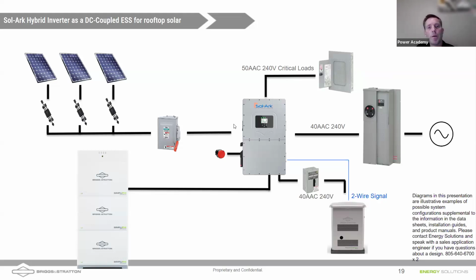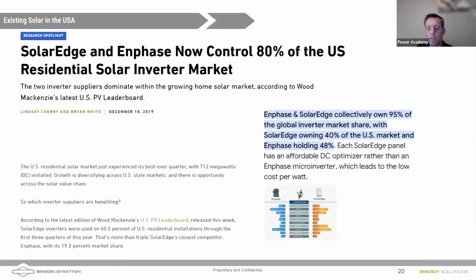This DC solar is then fed through a disconnect into the Sol-Ark. There's a rapid shutdown button there, and that Sol-Ark can use this DC power to either charge the batteries, or if the batteries are full, send that solar power out to the loads of the house, or if there's excess, send it back out to the grid. And we're also showing this Sol-Ark together with a generator that's there for a grid down event.